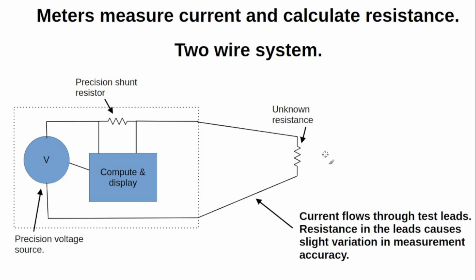The problem is the wires themselves, these test leads, have resistance, and anytime you have current flow across a resistor, you have a voltage drop. So the test leads themselves are going to skew the measurement slightly. In most cases, that doesn't matter so much—if you're just a hobbyist checking a resistor value, the small difference isn't going to matter. But if you want high precision measurements, then the resistance of the test leads makes a difference.